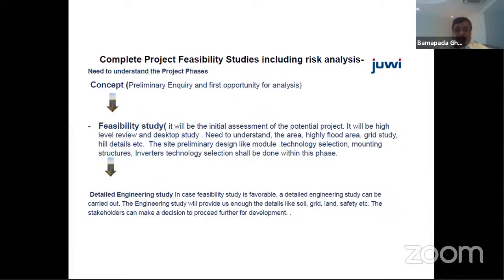Capital investment depends not only on the site but also on the perspective, like the grid perspective, what the DISCOM needs, and the grid codes. We need to understand the grid codes and the preliminary design, like module technology, inverter technology, and structure technology. If the site is a high wind zone, we will not select the single axis tracking system, and then we would not go for bifacial modules either, because bifacial modules require single axis tracking, and in the entire Southeast Asian region the tilt angle is very minimum, so a minimum tilt angle bifacial module doesn't make sense.